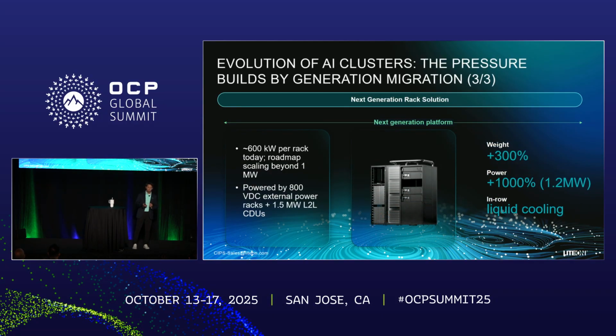Moving forward into 2025 and beyond, what we see is the rise of ultra-dense AI clusters, where the power requirement for a single AI rack now grows almost 10x, to 1 megawatt to 1.2 megawatt. That really is a key game changer. With that change, we also see that the payload per rack has increased 300%, and now the entire AI rack is liquid cooled.